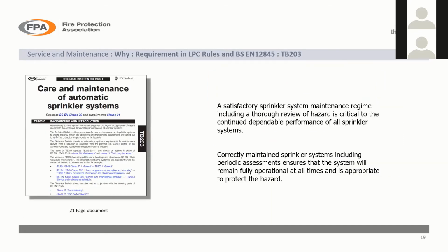Within the technical bulletins, TB203 is the main one, which covers the care and maintenance of automatic sprinkler systems. It's a substantial document. It's 21 pages long, and it goes into quite a lot of detail. I've just included the first few lines there to read from it, because I think it gives you the overall picture. That a satisfactory sprinkler maintenance regime, including a thorough review of hazard, is critical to the continued dependable performance of all sprinkler systems, and that's obviously very true.